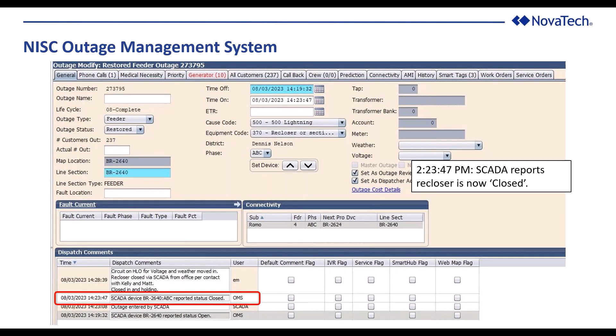So what hotline tag does, most of you probably know this: if it detects any hint, even the slightest period of overcurrent being detected, it opens the breaker instantly. It disables any reclosing functionality, so it's immediately locked out at that point. A weather system came in, something with the weather caused that current to go over the minimum trip, and it immediately knocked it out.